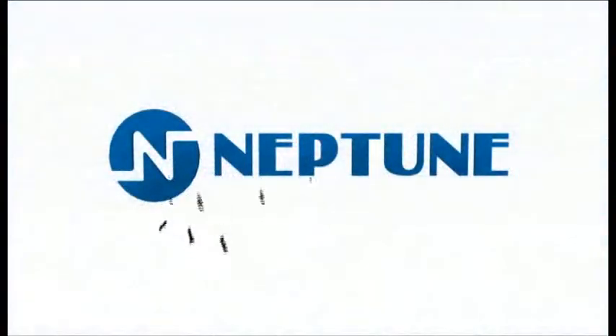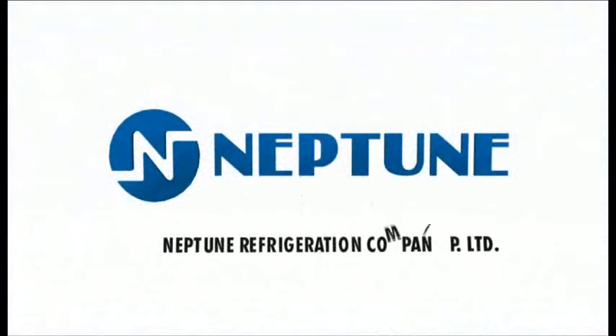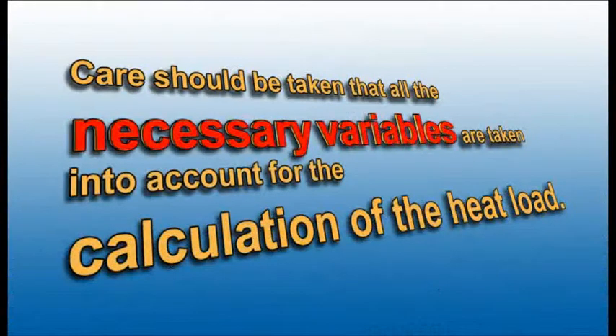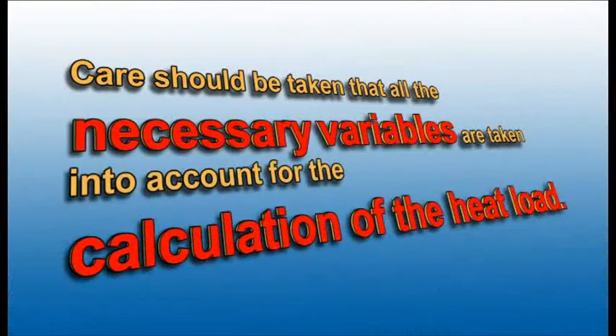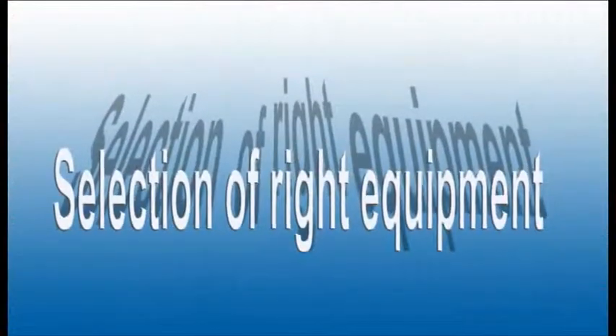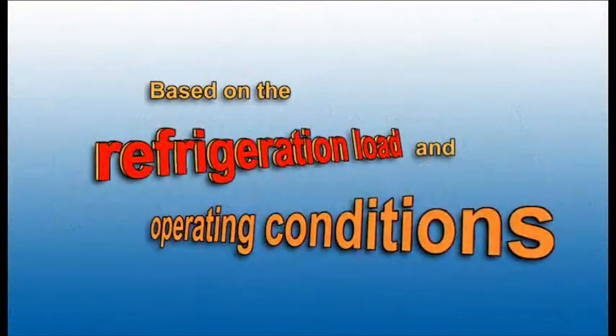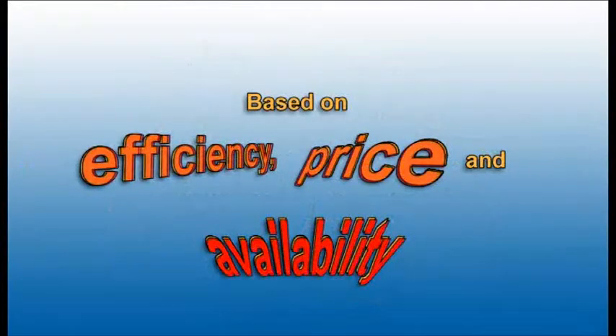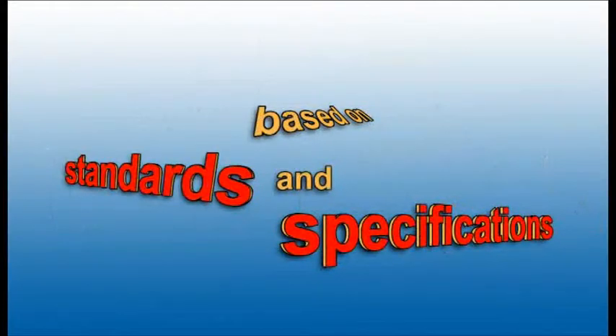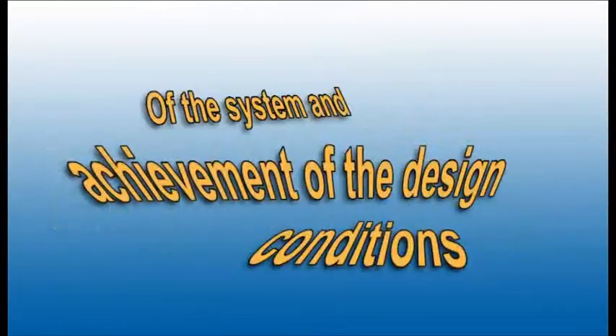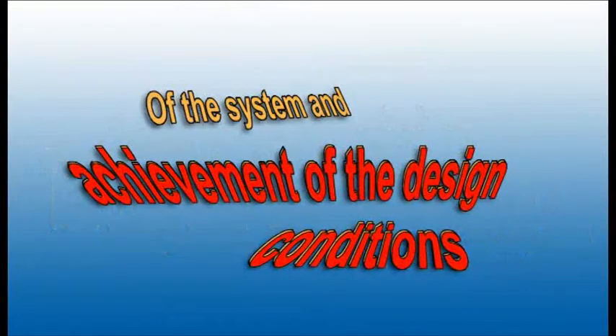Neptune ensures that in the designing of a refrigeration system, these crucial steps are followed. Calculation of the heat load. Care should be taken that all the necessary variables are taken into account for the calculation of the heat load. Selection of right equipment based on the refrigeration load and operating conditions. Selection of the individual equipment based on efficiency, price and availability. Installation of the equipment based on standards and specifications. Testing and commissioning of the system and achievement of the design conditions.